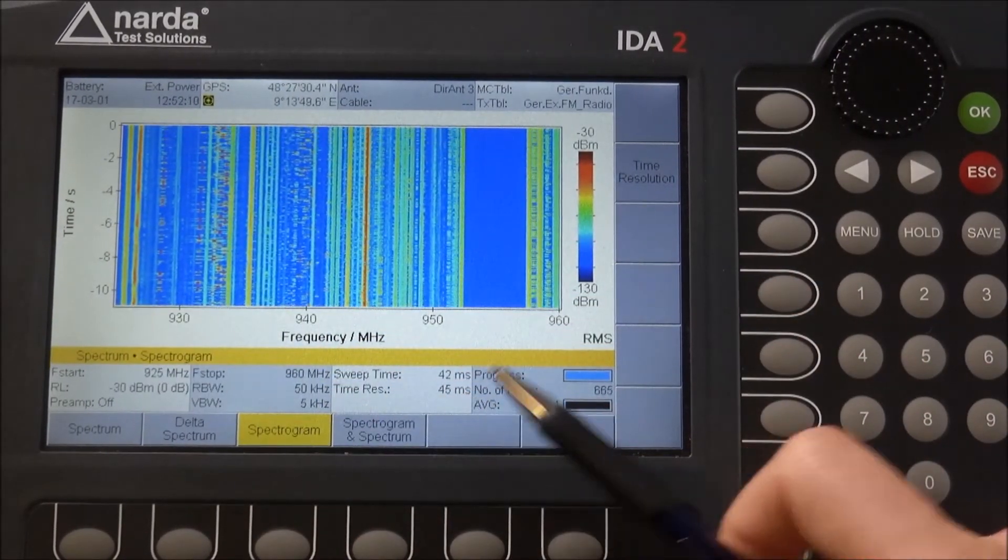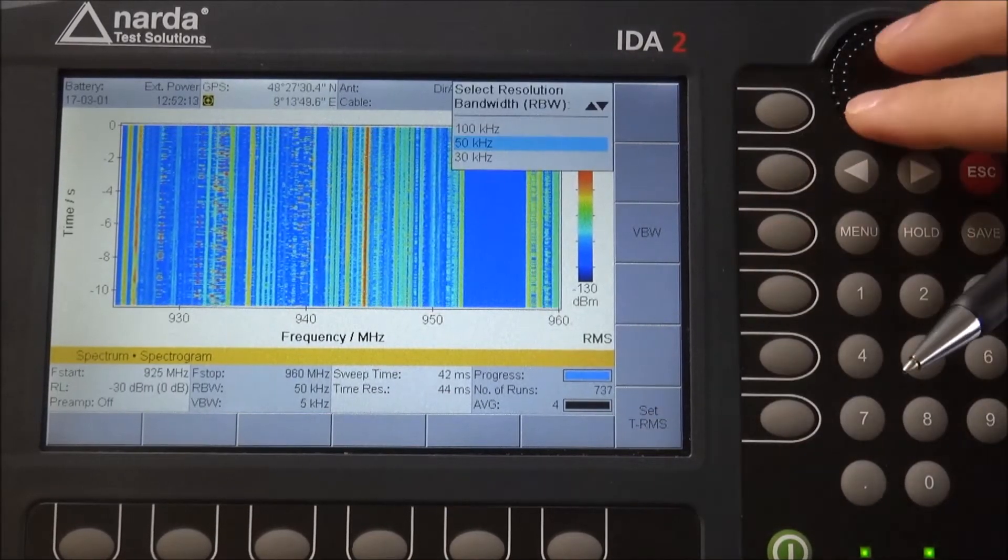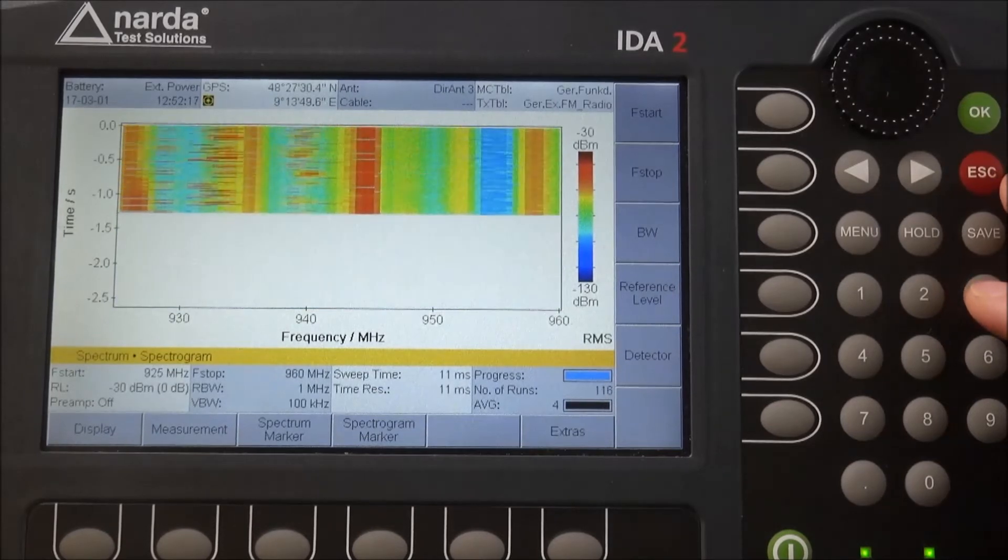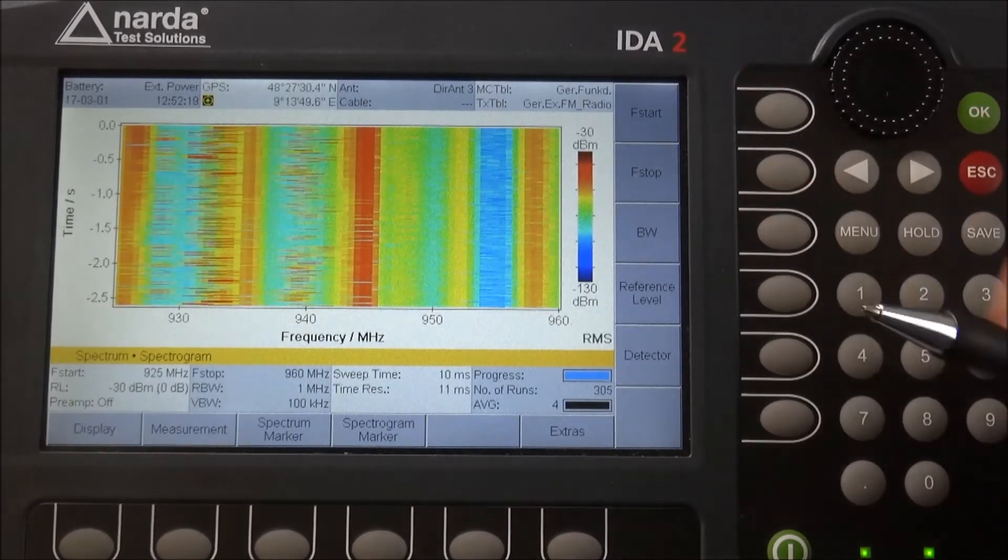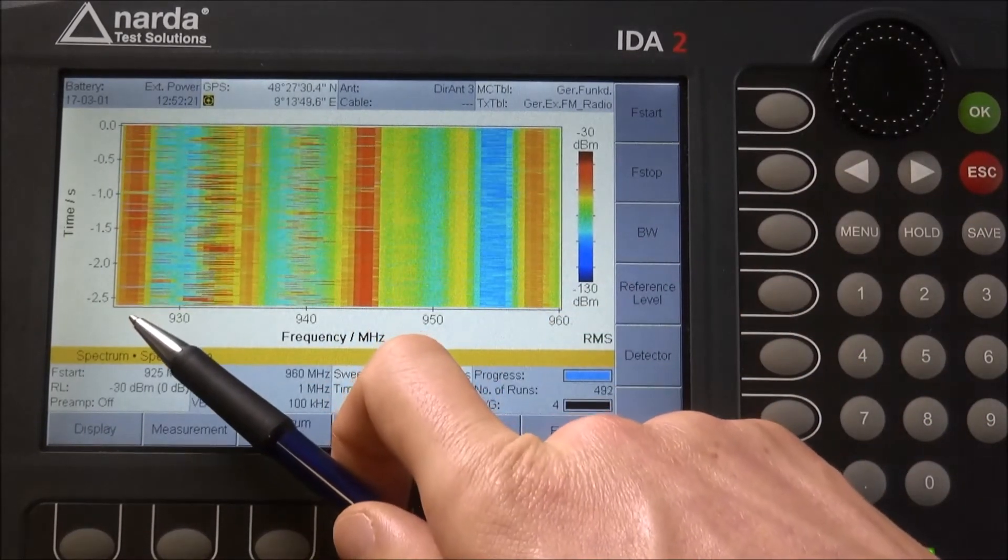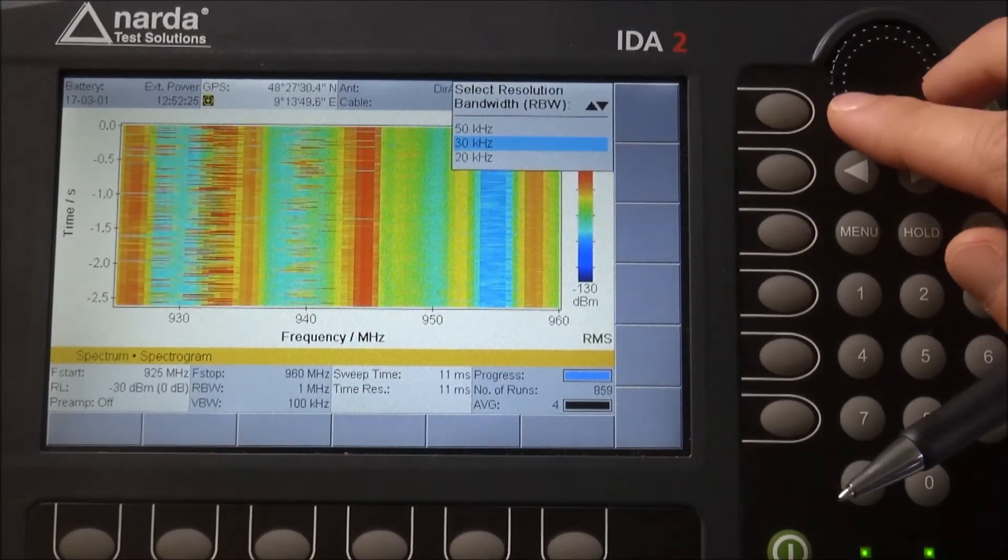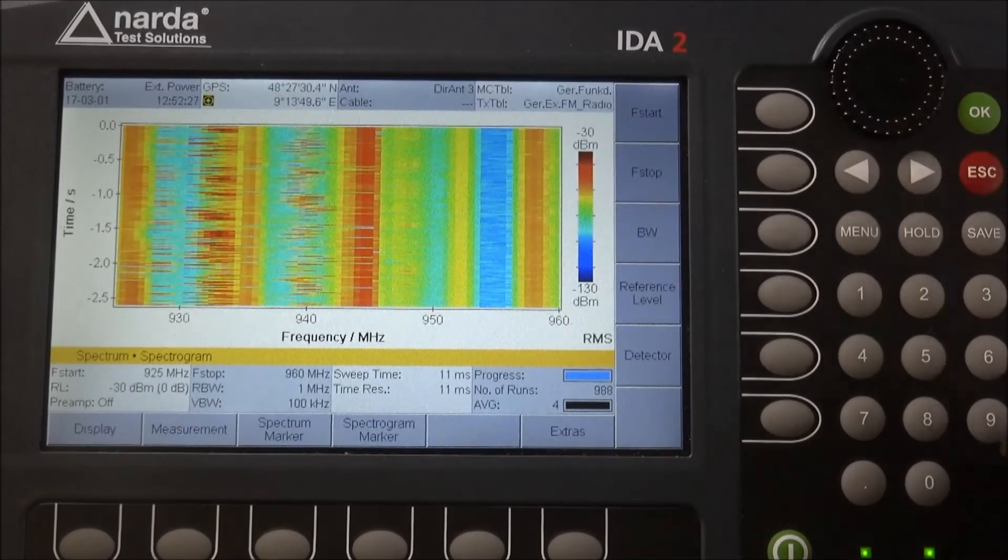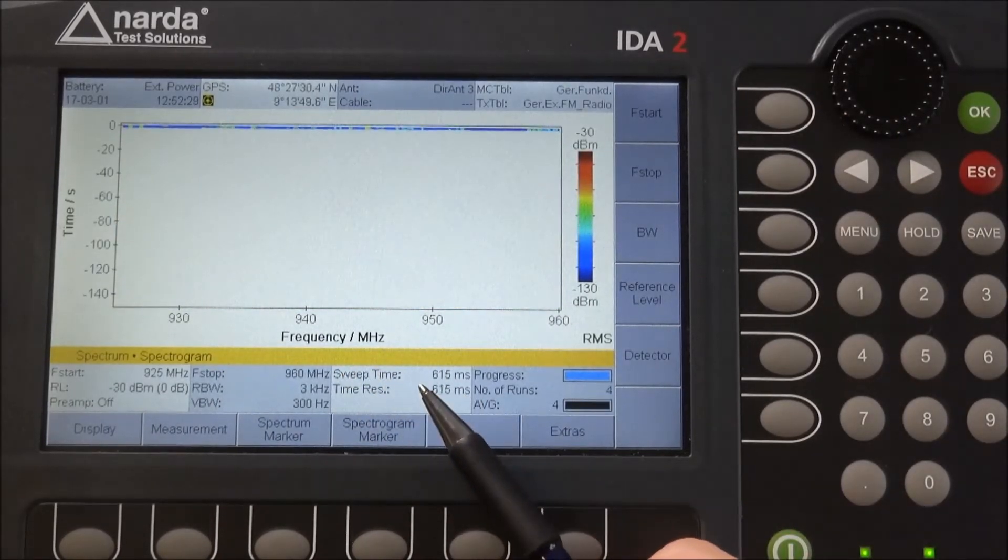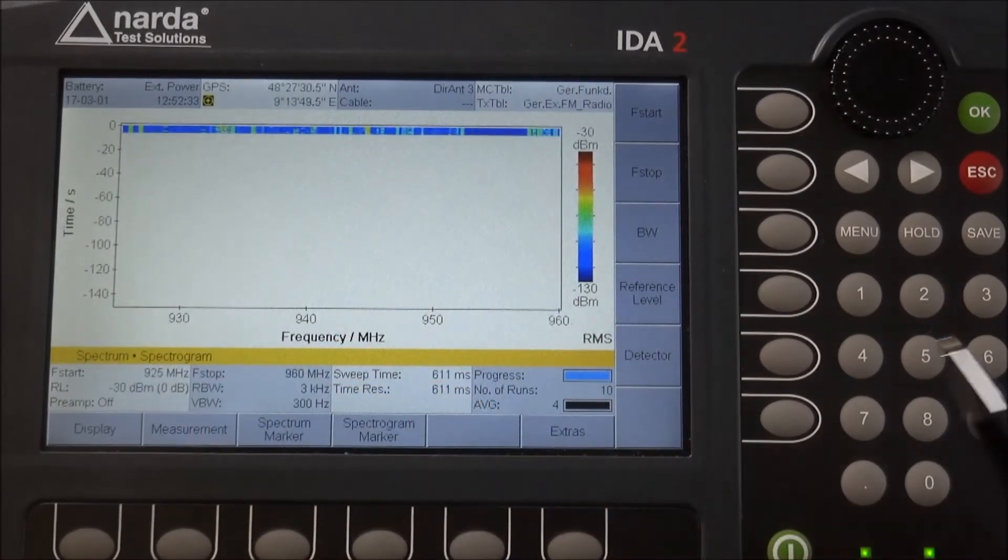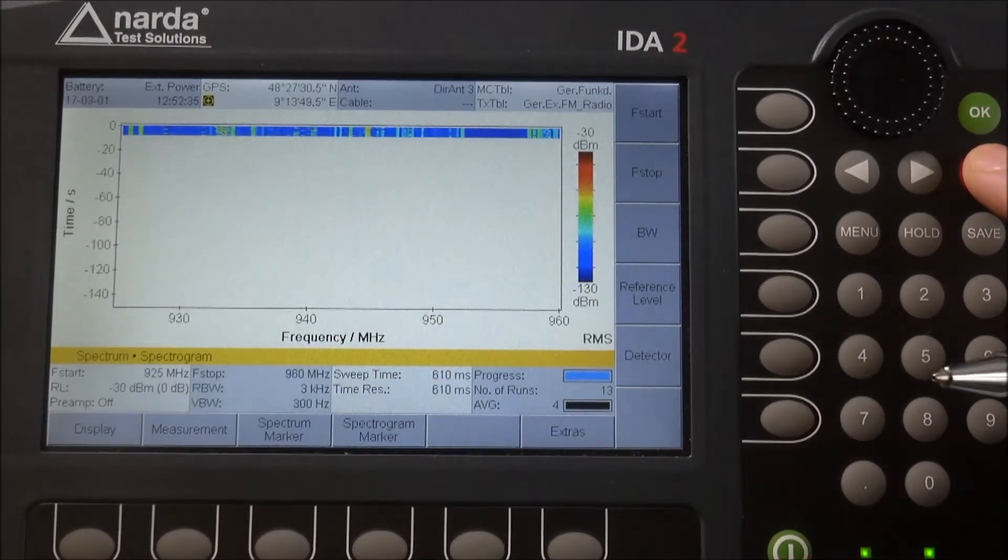By increasing the RBW to one megahertz, our displayed spectrogram becomes shorter. If we take a very narrow RBW and the sweep time increases, the scaling in our spectrogram also increases.